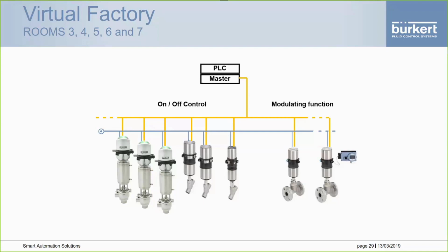And it really leads me to say I do recall one particular project where we did the analysis of a hardwired installation versus a field bus installation or an intelligent installation. We sat down and calculated the need for all the termination points. These termination points were between the PLC, the I/O cards, the field marshalling terminals and the field junction box, and all the way back to the feedback head in the field. We counted 32 termination points for every single process valve in the field.